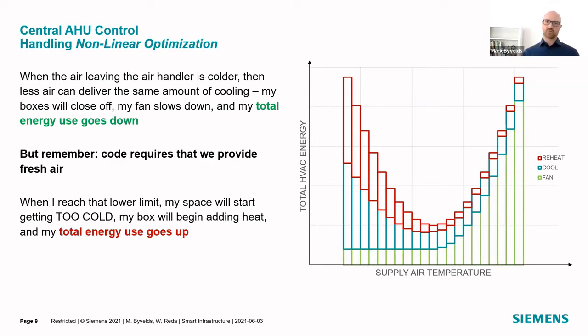On the far left, we're supplying very cold air, so we don't use as much fan energy because our variable air volume boxes aren't asking for that much, but we use more energy on our chiller or cooling system to make it that cold. And if that's the case, we probably have more zones that need reheat because the supply air is colder than the zone needs.